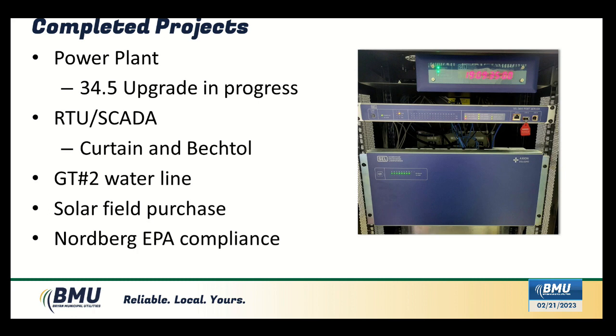The RTU and SCADA at Curtain and Bechtol are done. There's a picture of the new SEL system in there. It's trouble-free now—we used to have those drop out all the time randomly, and now we can communicate with them very easily. The GT water lines give us extra cooling on the oil on really hot days, which makes the generator run cooler, and anything spinning runs better cooler.